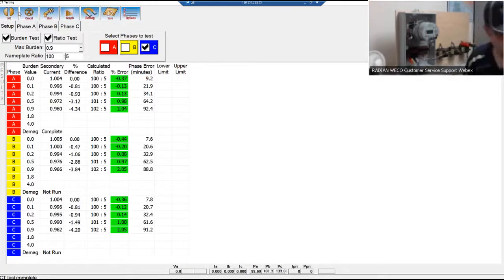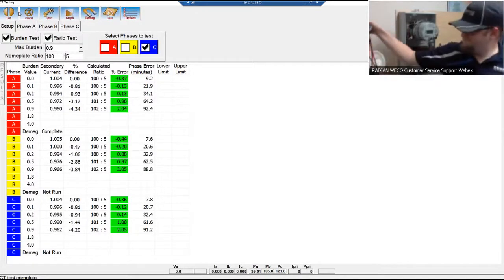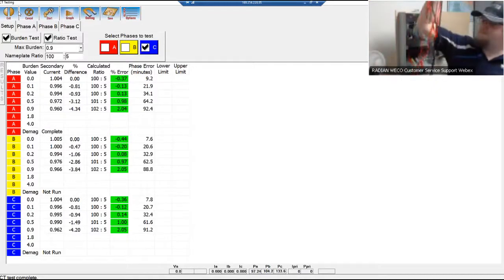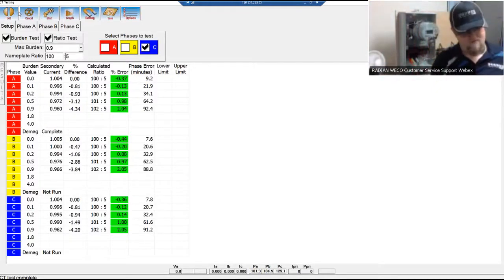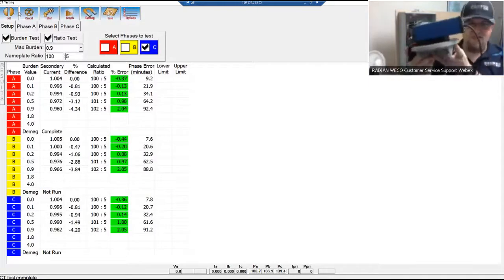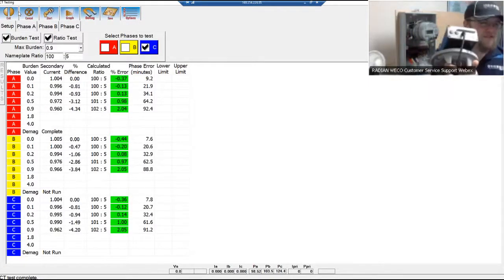Now going into the differences between the Bantam Plus and the RW. The RW has CT testing built into it. Bantam Plus requires an accessory to do so. That accessory is called the RB-TSBR1. It's the Bantam burden ratio CT test. And it looks something like this, with a bunch of cables in it. So this is our TSBR1, Bantam Plus CT burden ratio test.